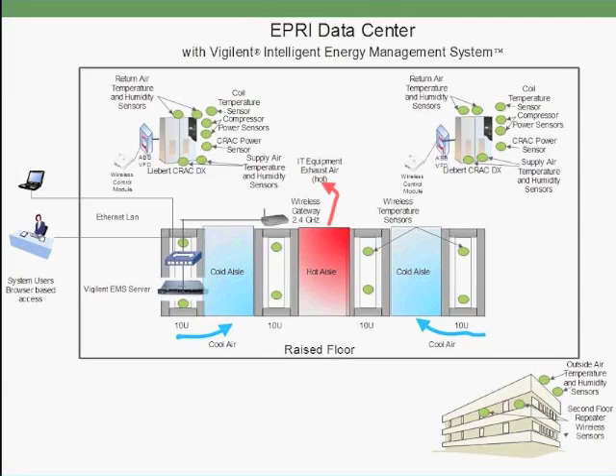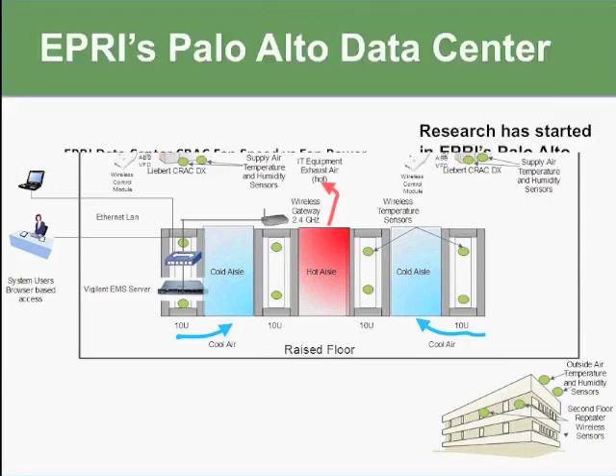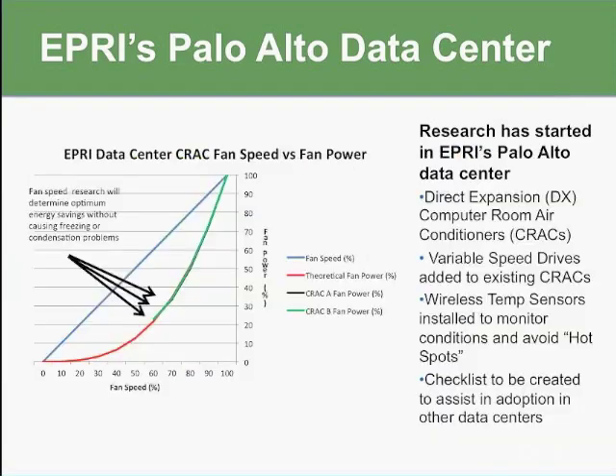There was a lot of concern that the motor wasn't rated for that. If you take these DX units and you slow down the airflow, there's concern that you're going to have all sorts of condensation and freezing problems. When we installed these variable speed drives on the fan motors, we slowly decreased the speed of the fans and took a look at what the energy savings was.